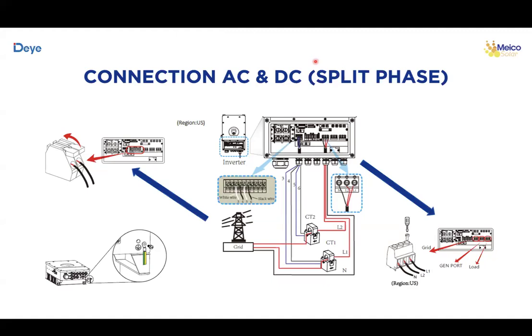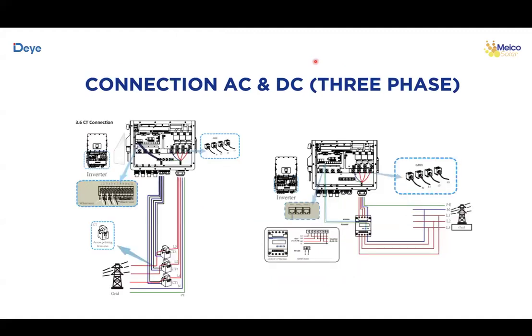Okay, let's go to the three-phase connection. In this case it's the same. The inverter inside looks very familiar and similar to a single-phase inverter, and you will have the same connection — the grid connection and all the connections for the CTs. In this case you will have three CTs as it's a three-phase connection. You will have this place to connect your genset, and as well the place to connect the main loads you want to cover.